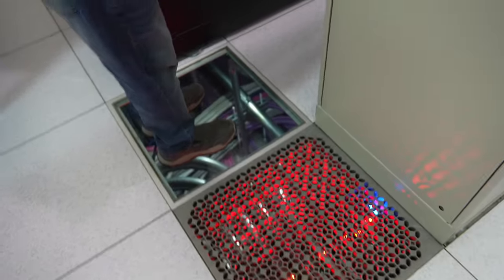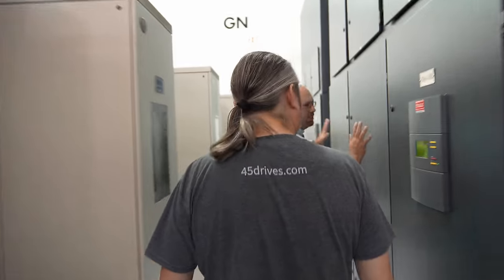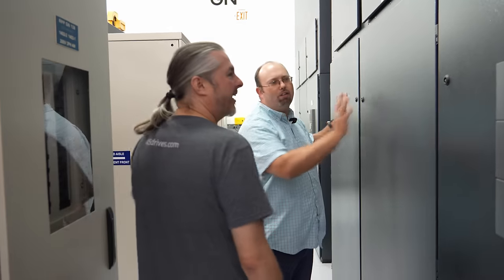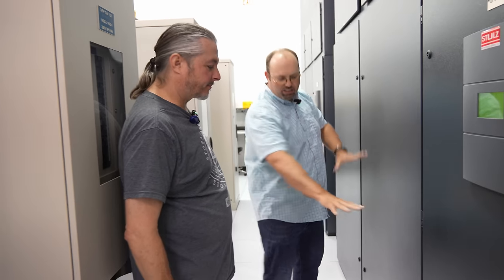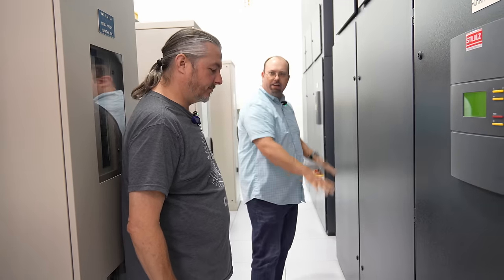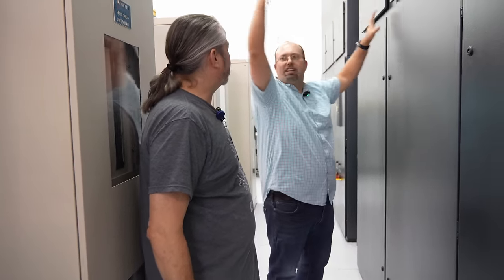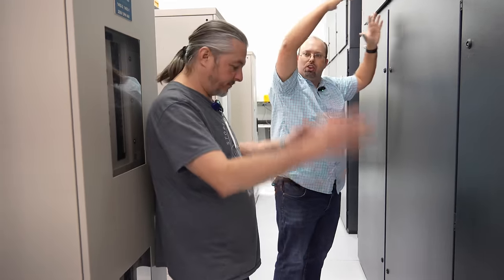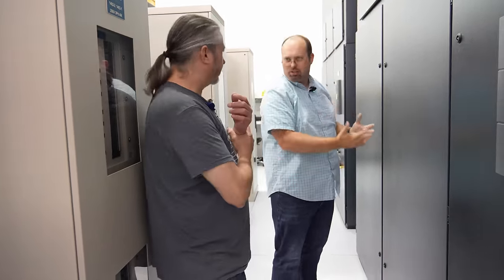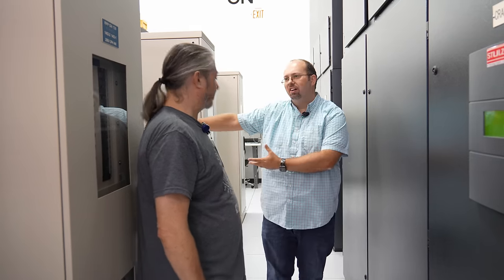This is a 40-ton computer room air handler. It has a large radiator coil and variable-speed fan motors on the underside, baffled to capture the hottest air possible — because the hotter the intake air, the more efficient the thermal transfer to the cooling loop. More heat offloaded means colder supply air on the other side. That's how you solve the cooling problem at scale.